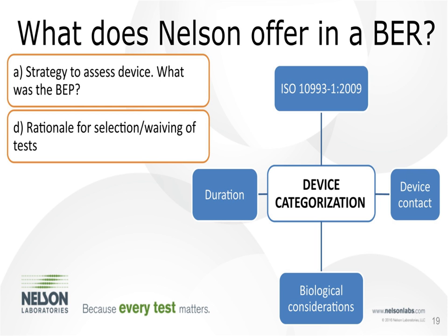The next section is Device Categorization, based purely on ISO 10993-1: device contact, duration, and typical biological considerations. We'll also include any parallel standards — for example, cardiovascular devices or gas pathway devices may have additional standards with further considerations. For the points covered in Clause 7, we're addressing the BEP, discussing which endpoints need to be addressed and why, and justifying which tests were or were not performed based on those parallel standards.